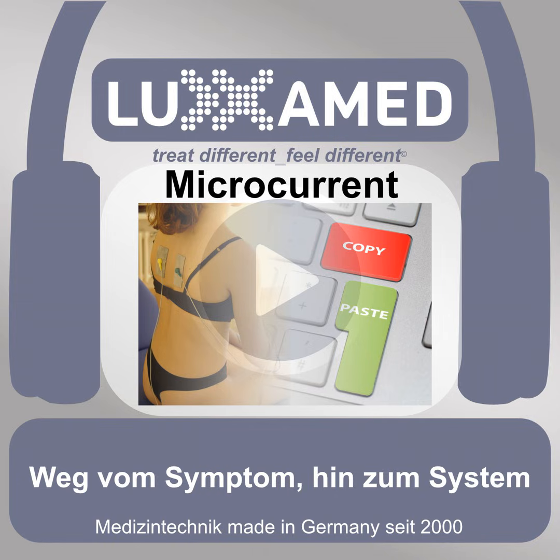And the question is, can the channels interfere with each other? For example, if you combine several placements at the same time. For example, a local placement on the knee, and at the same time a lymph placement. The answer here is quite clearly no. We have always had galvanically isolated circuits, so interference between the channels is technically simply not possible. Neither constructive nor destructive interference. So you can combine several strategies at the same time without hesitation, without the channels influencing each other.